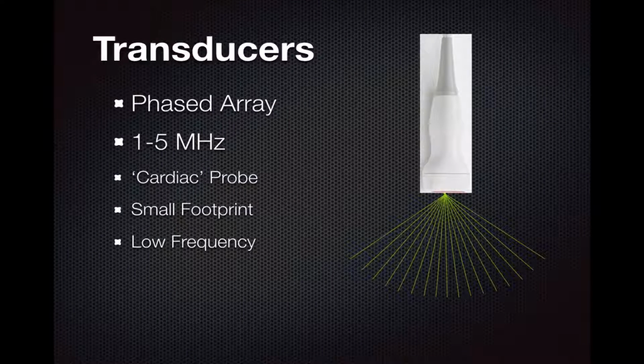The phased array probe, or the cardiac probe, is also a pretty low frequency probe, 1 to 5 megahertz, really designed to see motion well. And also it's a little bit different, where the sound waves just originate from the very middle of the probe, which makes it really good at shooting in between ribs, and one of the reasons we like to use it for cardiac imaging.